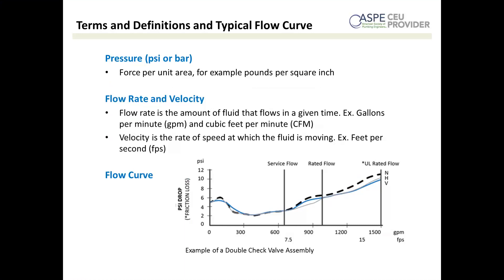Here we have a flow curve, typically published as part of your engineering or specification sheets with a backflow preventer. This shows pressure drop due to friction loss across the device as a function of flow rate or flow velocity. In this case, this is a double check valve assembly — this can be thought of as the performance of the valve, and it typically goes from zero to 25 feet per second.